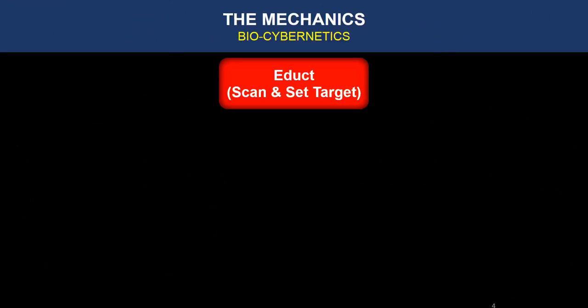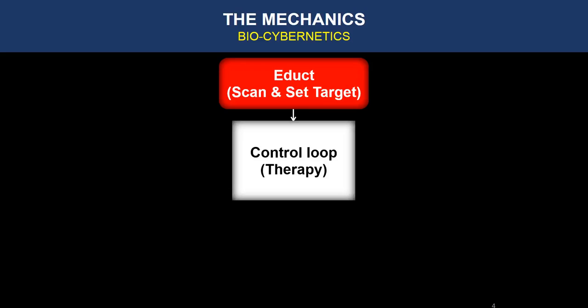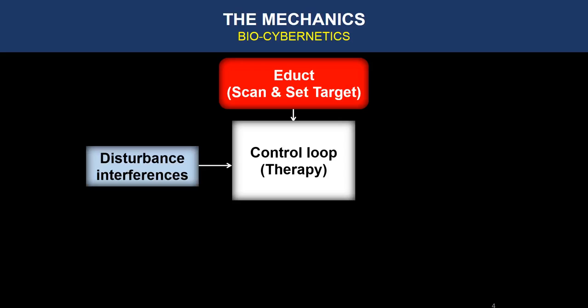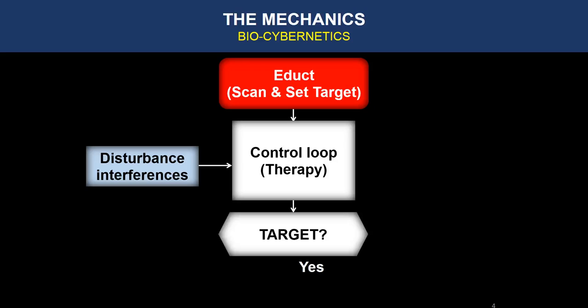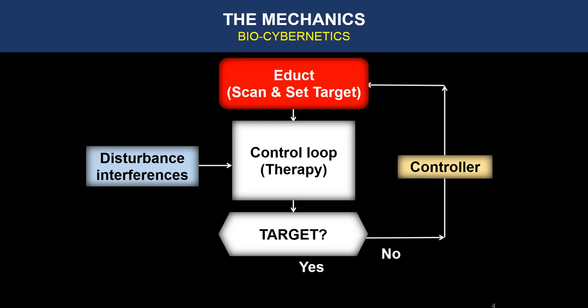The machine goes into these procedures. First we call educt — this is the stage where it scans and the machine itself sets the target to achieve. Then it goes into the control loop; this is the actual therapy that's happening. And there will be some interferences from outside, like the movement of the patient or maybe the electrodes coming out. Then the machine actually looks for whether it has achieved the target. If the answer is no, it goes back to the first stage where it scans again and sets a new target.